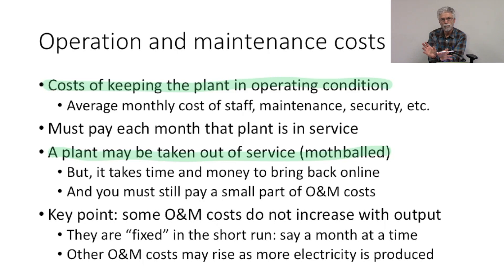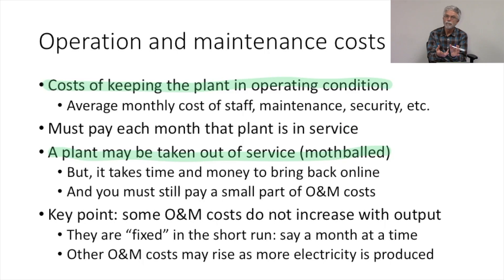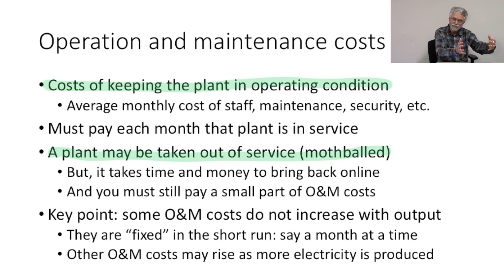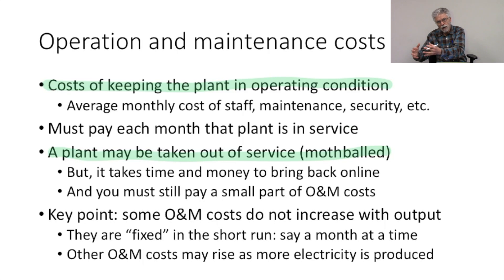Some operation and maintenance costs will actually get larger the more you run the plant. For example, the more you run a generator, the more maintenance you're going to have to do on it. If it's not running at all, you won't have to do much routine maintenance. If you're running it a lot, you'll have more routine maintenance to keep it running. So we have different types of O&M costs: some more or less fixed, some fixed only if you're running the plant, and some that vary as you run the plant more.